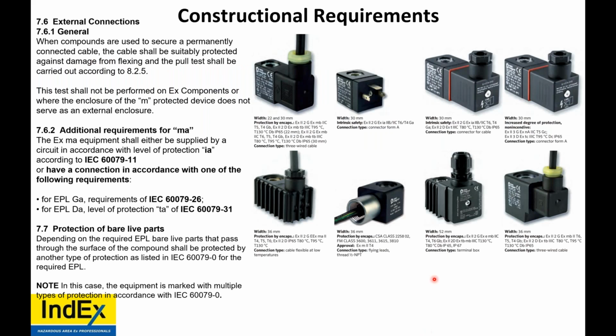So, of all these solenoids, this one's EX m, this one's EX m, this one, and this one. The top 3 on the top row right are not. But as you can see, their construction is very similar. You can have ones where there's no cabling and you have to wire it up, or it comes with the cabling being intrinsic to it. Ones where it is intrinsic, but it could go on a threaded conduit, or a cable gland that you provide goes into it. Or once again, it's integral.